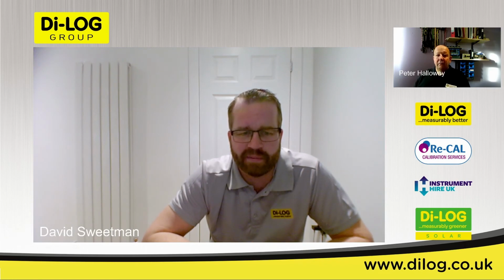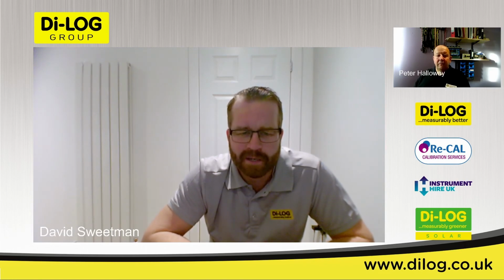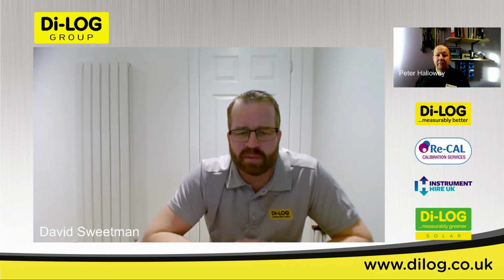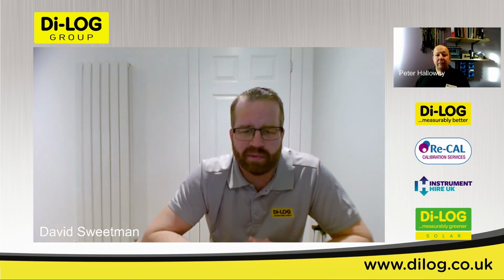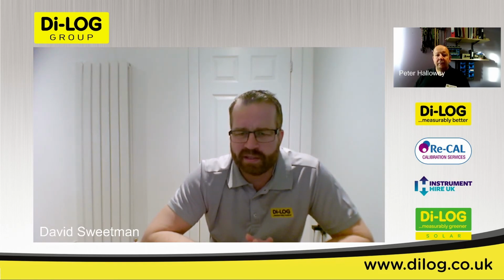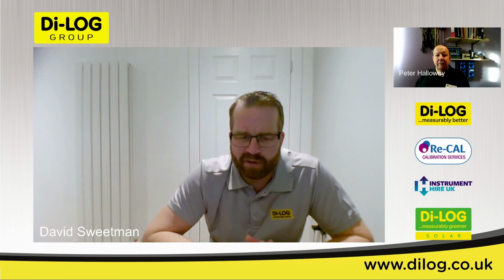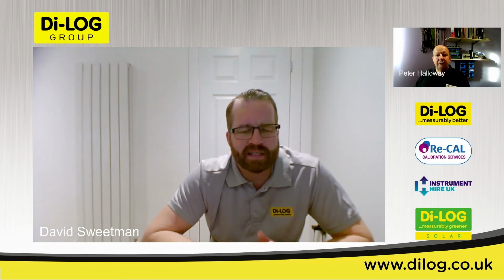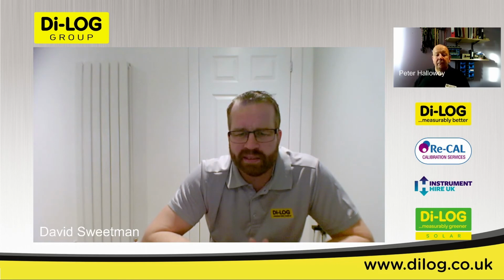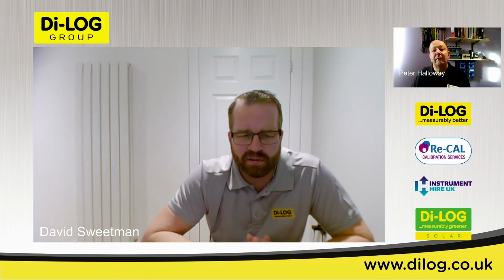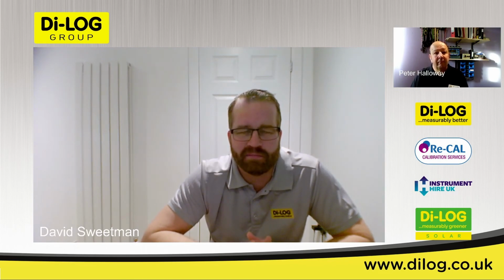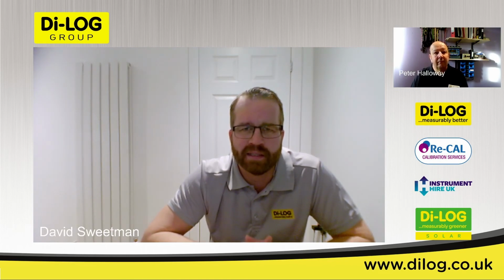Energy monitoring and phase balancing are particularly important as well. I've attended several seminars with you, Pete, and one thing that always sticks in my mind, which you mentioned earlier, is non-linear loads. A great example of this would be installing LED lighting in place of the old incandescent or fluorescent lighting from yesteryear. Ironically, although there are huge energy savings from adding LED lighting to an installation, the implications of non-linear loads like LED can cause really poor power factor, and it's phenomenal how much of this is out there.